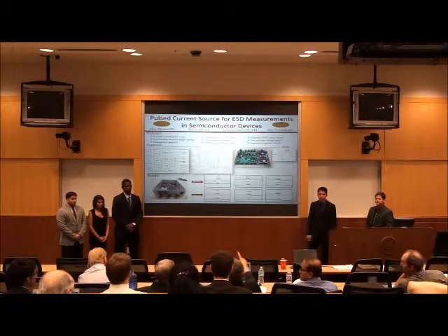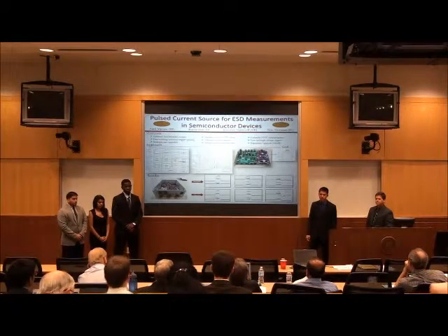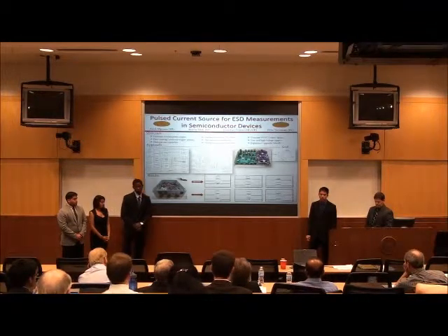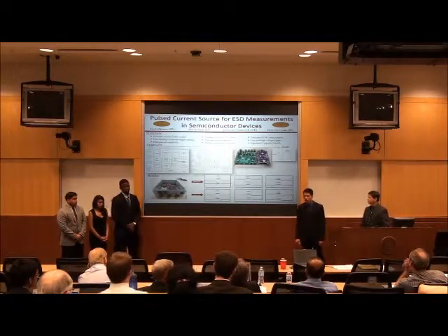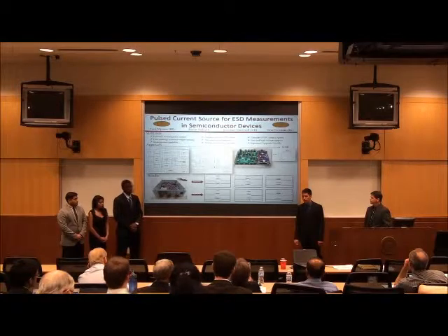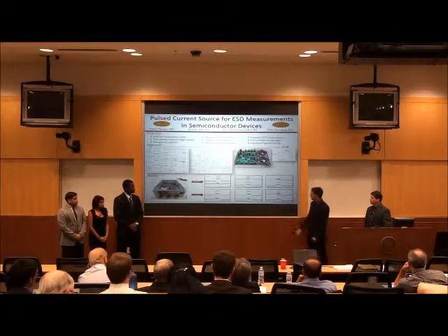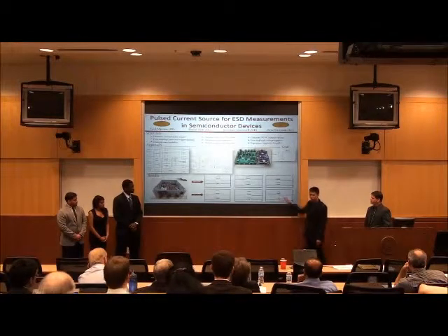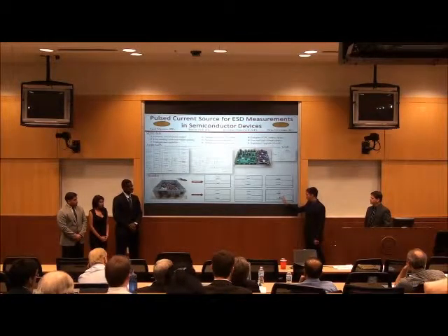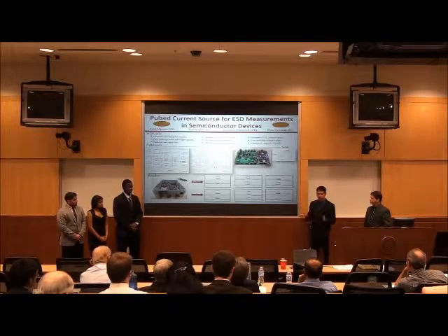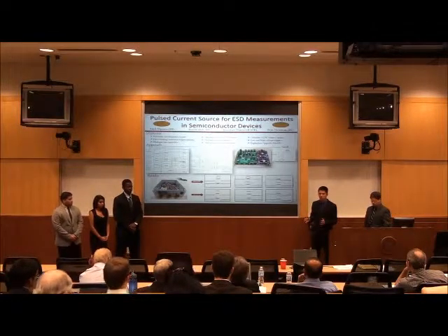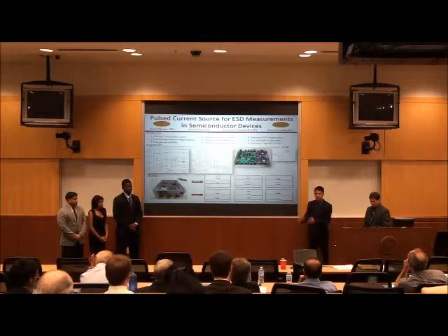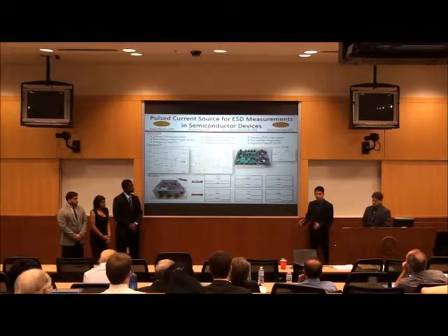Did you see the impact of the ringing? Does that distort the measuring result? I'm sorry, is it the ringing of the signals you see? There's a substantial overshoot. Does that impact the actual analysis? Well, the main thing we're looking for is the energy of the whole entire pulse. By varying the pulse width, we can change that energy as well. So we have many options to change the energy. That's what we're looking for, the energy of the electrostatic discharge.